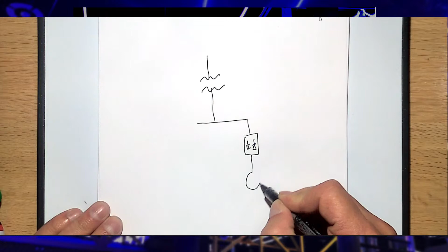What's the VFD going to do? It's going to produce harmonics, and we say that harmonics flow out of the load into the system. So they flow up here, and where do currents want to flow? Current wants to flow the path of least impedance, right? So there's no other path, so it's going to go out. And people think harmonics flow to ground. They don't. They flow out on A, back on B and C, out on B, back on C and A, and so forth.